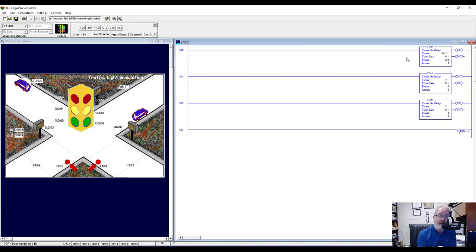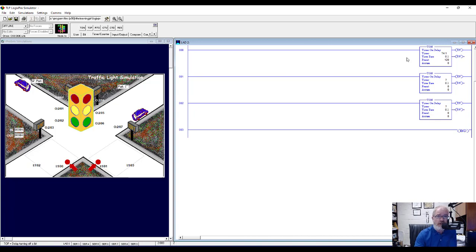That's how timers work with Allen Bradley and most any other PLC — if they have a time base, you have to be careful with preset values. The newer Allen Bradley PLCs, like the 5000 series ControlLogix PLCs, have a fixed time base of milliseconds, so for 12 seconds you'd put in 12,000. But Logix Pro uses the old SLC 500 series, and Allen Bradley time bases are variable — you can set them to a few different options.